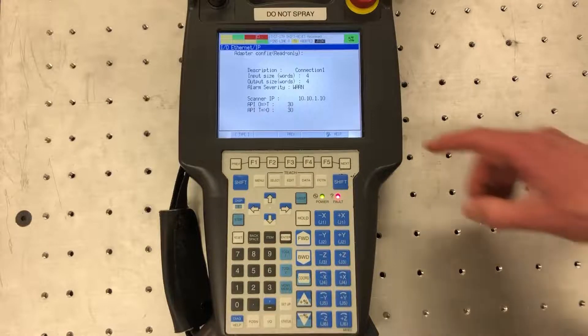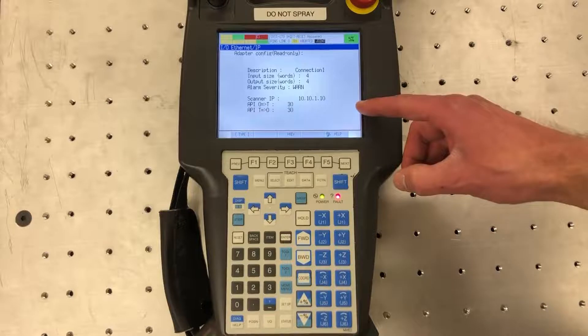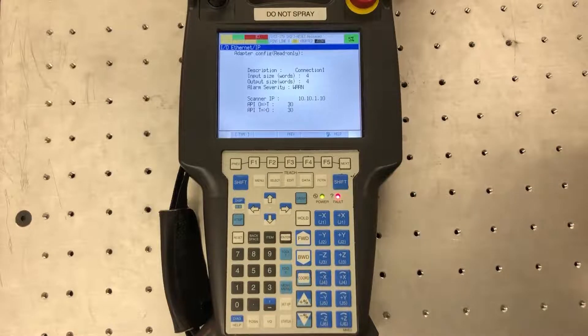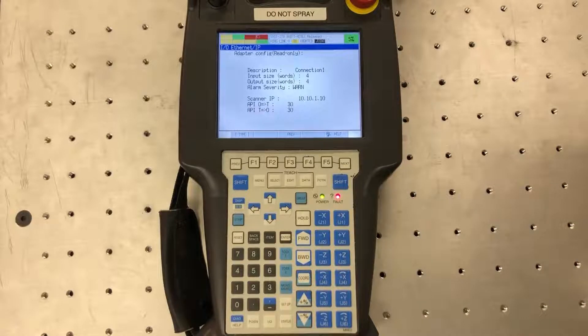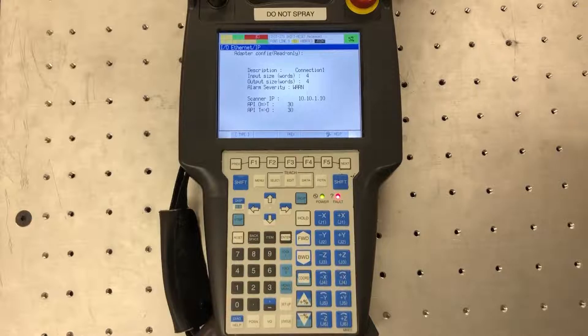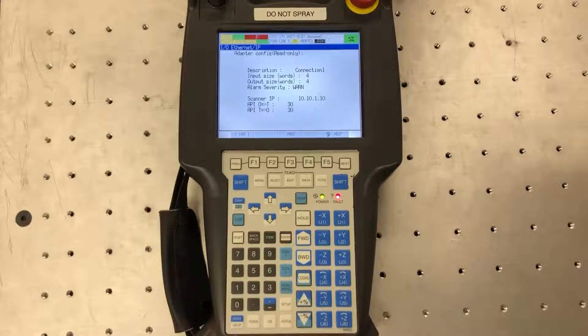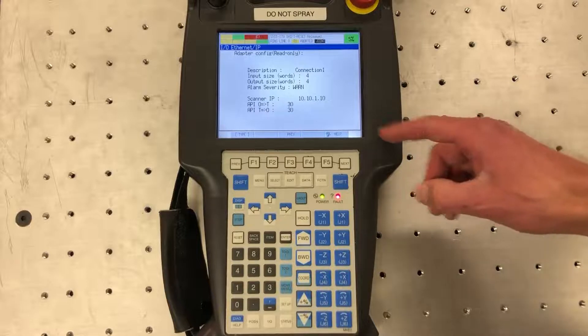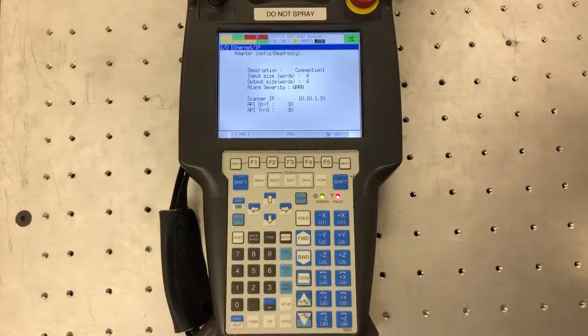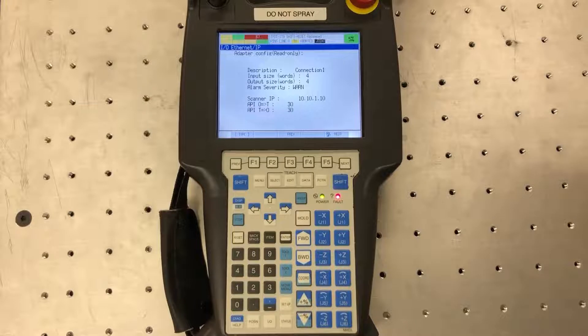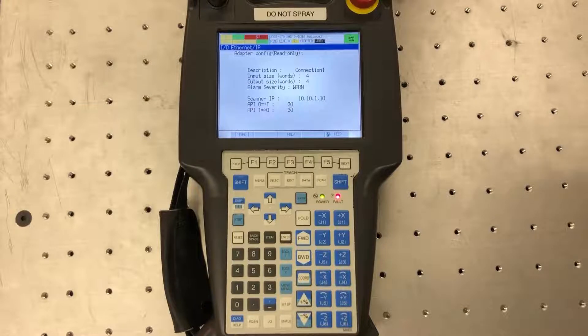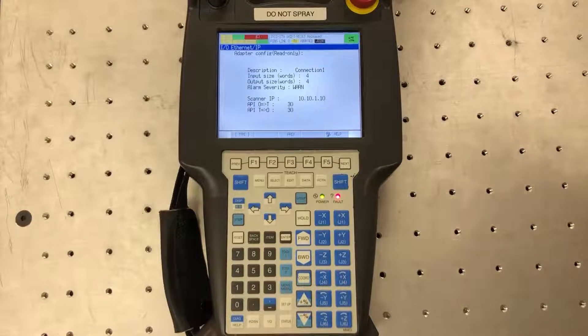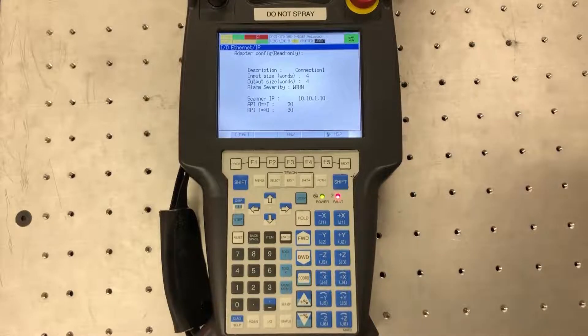Down here where it says scanner IP this will auto-populate so you will not have to set these. As you can see mine is connected to the PLC right now so it auto populates the PLC IP address. This RPI references the speed information is transferring. In the PLC I set up the requested packet interval as 30 milliseconds, so this is also auto-populating to that.